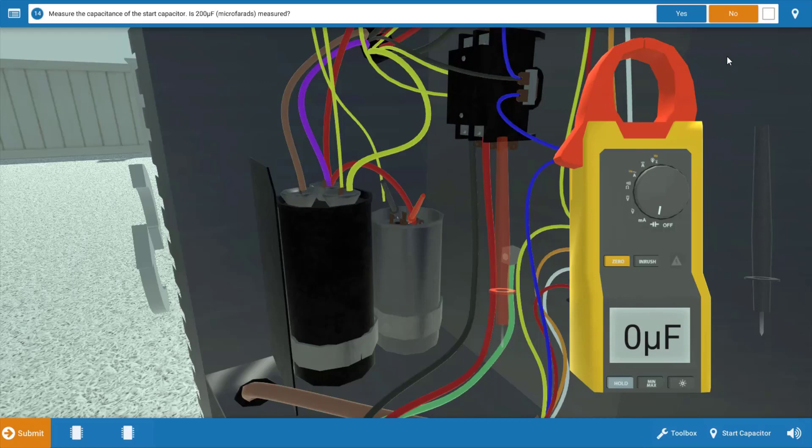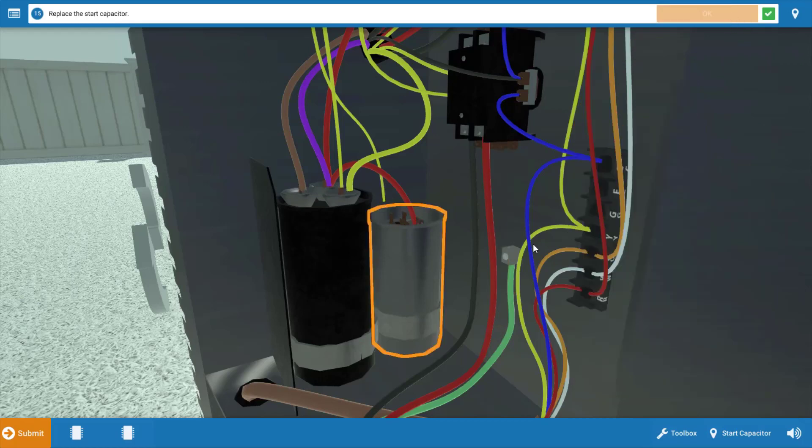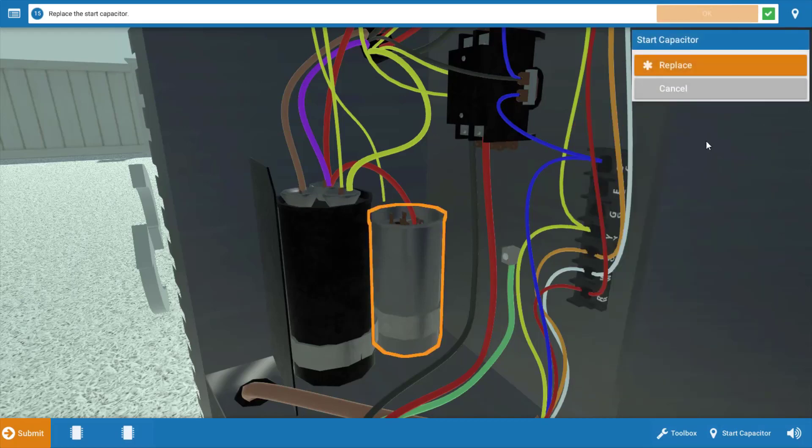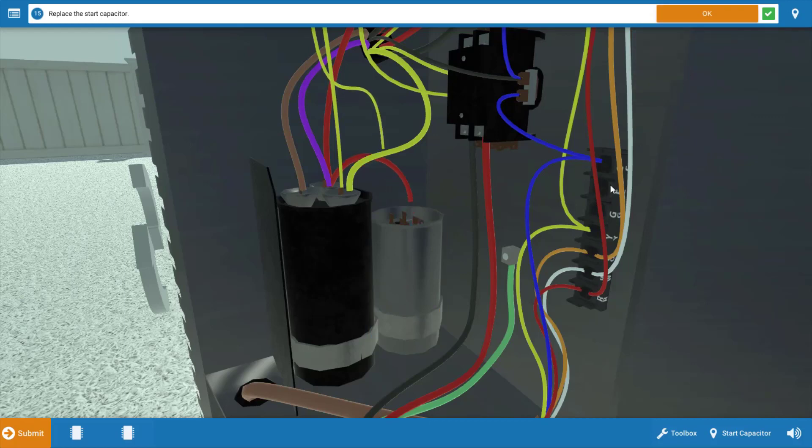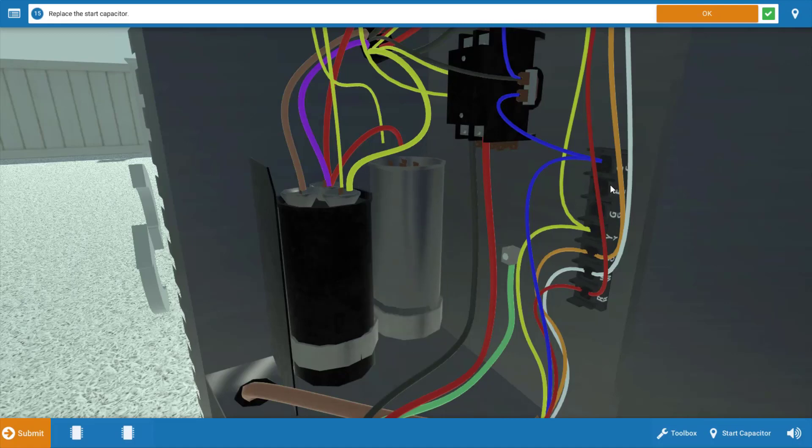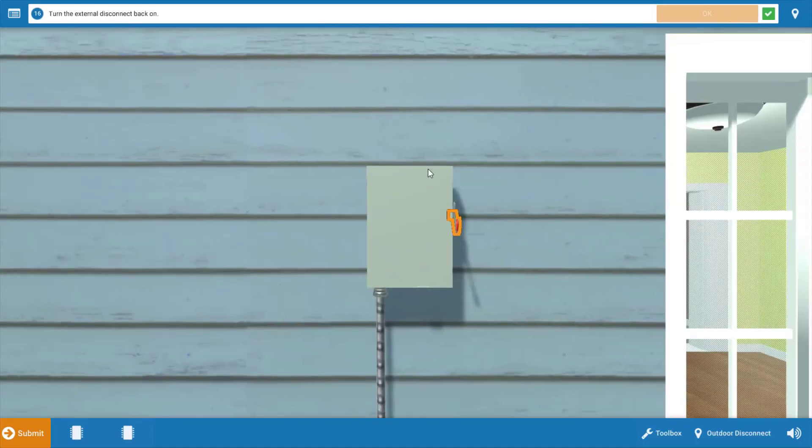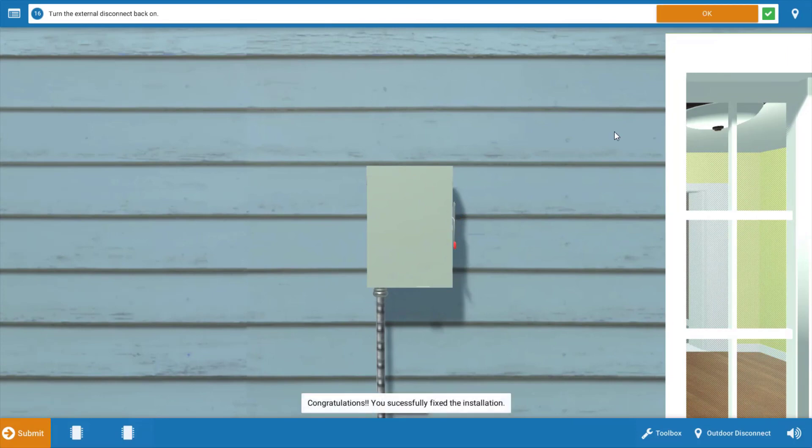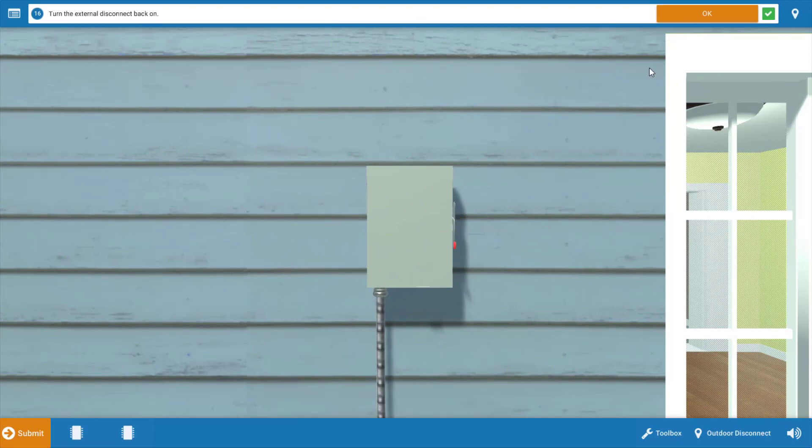So we're going to click no on the procedure guide that we didn't measure 200. We're going to click on that start capacitor, click replace. And once that problem is fixed, it's going to be necessary to reconnect everything securely and turn the power back on. Once you do that, you want to observe one full cycle of operation to make sure all loads are operating properly.